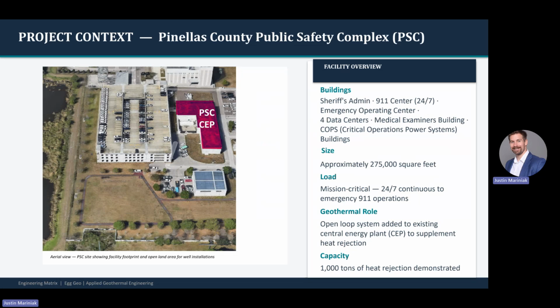The project we're looking at is the Pinellas County Safety Complex. This building functions as a Sheriff's Administration building and Emergency Operations Center. It is classified as a COPS building, which means Critical Operations Power Systems. The building served by the geothermal system is nearly 300,000 square feet in size. It requires 24/7 continuous operation and functions for emergencies. There is a potential of 1,000 tons of heat rejection for the geothermal system. For reference, a typical home is 3 to 4 tons of heat rejection or air conditioning.